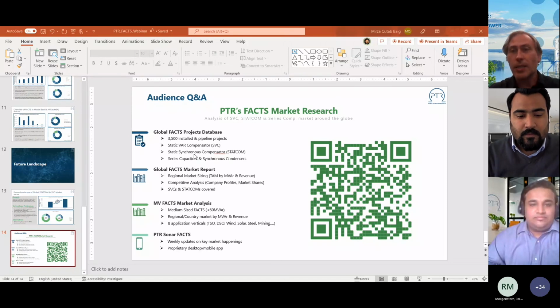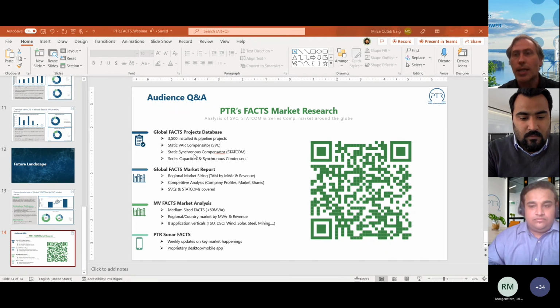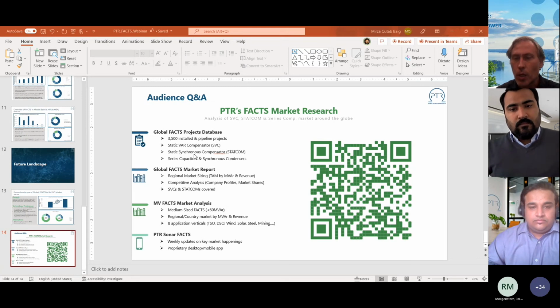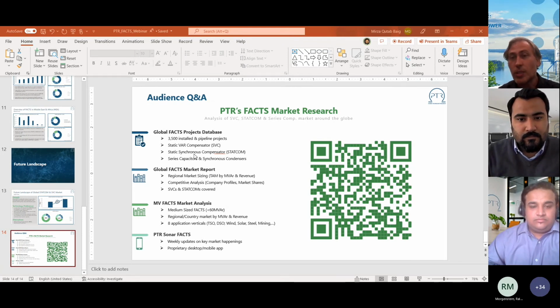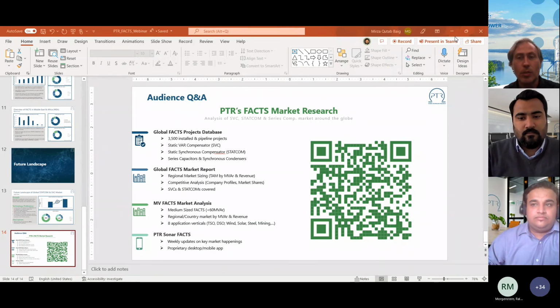Yes, I think there's still demand in the industry for FACTS devices in the future also. Industry, we can understand as steel mills, rolling mills, mines, and any kind of industry that is handling big loads or very fast changing loads. So passive harmonic filters are also a solution in these kinds of cases, but basically for harmonic filtering. What FACTS or STATCOMs bring to these applications in industry is also the control of the reactive power, the improvement of the power factor, balancing the loads, mitigating flicker, and so many other things that passive harmonic filters just cannot do.